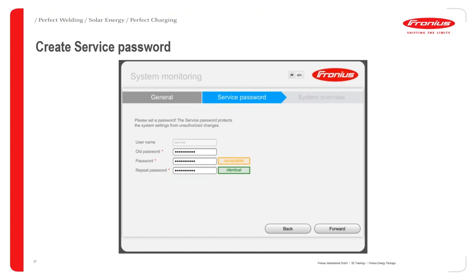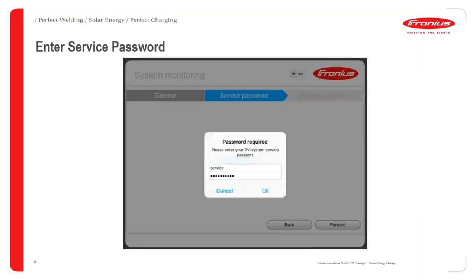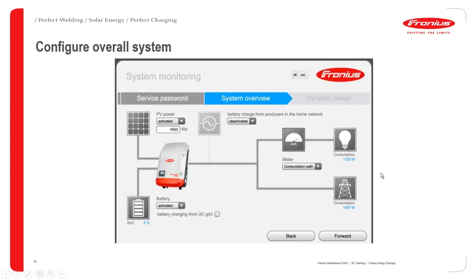The next step is setting the service password. In here, because we've set this up before, it has the old password there, but in a new system you would just have the lines there, password and repeat password. To set up the service password, the service username is service, and possibly you could use something like service123, or use something that you're going to remember, but you want to use something that essentially doesn't get used by the end customer, because this is a section where you can actually adjust and set up export limiting, so that's why it's a separate password for this section.